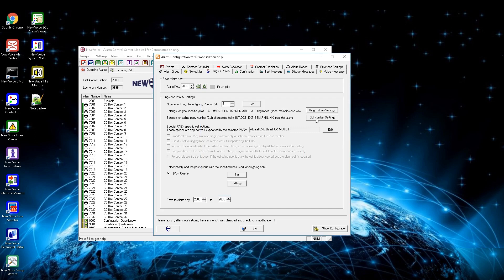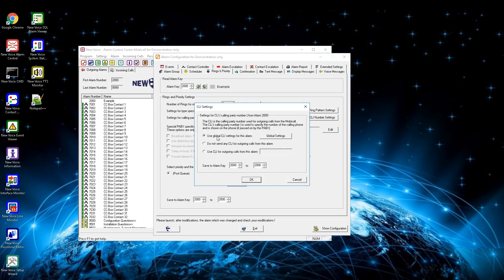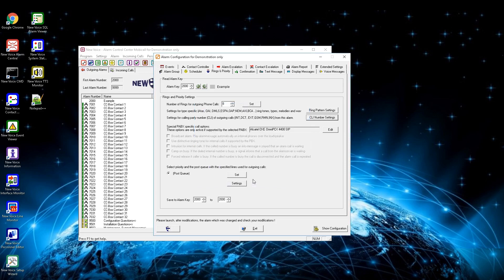By pressing the button CLI number settings there are three options: first, to use the global CLI for every alarm (by default it is MobiCall); second, to not send a CLI for this alarm so the call will be shown as a suppressed user; and third, to send a specific CLI for this alarm so every alarm shows a different number on the receiving phone — useful when alarming GSM phones since it is not possible to show any text in a call to a GSM phone. The next options are only active if supported by the PBX: broadcast the alarm (MobiCall opens the speaker and broadcasts the message), activate a distinctive unique ringtone for internal calls, and intrusion (where MobiCall opens an existing voice call and speaks the message on a third channel — be careful with sensitive voice messages).